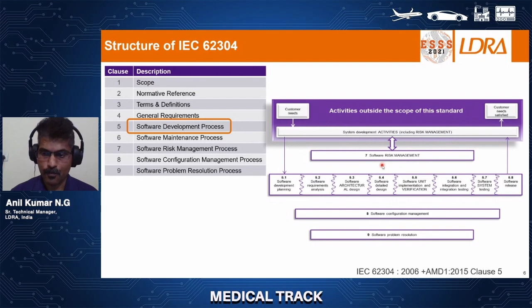Now let's see what the structure of IEC 62304 is. 62304 basically consists of 9 clauses: scope, normative references, terms and definitions, general requirements, software development process, maintenance process, risk management process, software configuration management process, and software problem resolution process. Over here, we are clearly highlighting the software development process, wherein you can see the various activities which need to be completed as part of it. We have software development planning, software requirement analysis, and so on towards the software release. We do have the software maintenance process, which will be more or less similar to the software development process mentioned here, but there are a few additional things which have to be taken care of as part of the maintenance process. And the software risk management process has to be performed all through the software development lifecycle as well as in 62304.